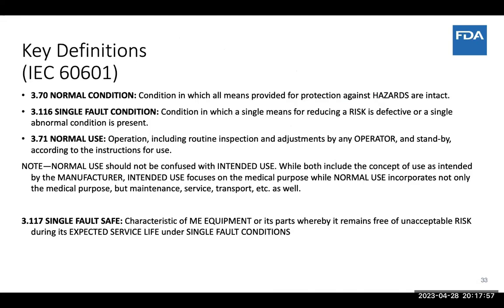This is a standard called IEC 60601. You can look up these numbers and it describes using a device under normal condition versus single fault condition. If you have a device doing something sensitive—say it uses sensors for something critical—you want more than one sensor, or more than one way, to protect against something bad happening.